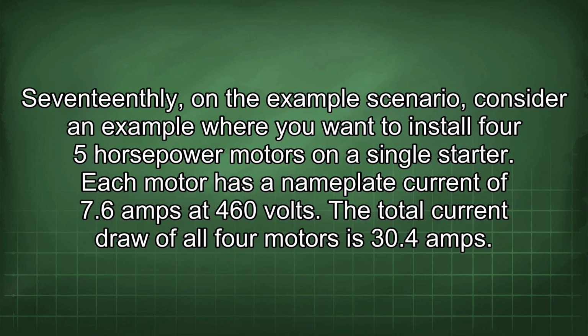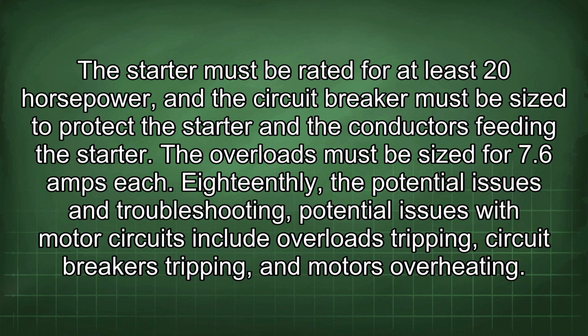17thly, on the example scenario, consider an example where you want to install 4 5 horsepower motors on a single starter. Each motor has a nameplate current of 7.6 amps at 460 volts. The total current draw of all 4 motors is 30.4 amps. The starter must be rated for at least 20 horsepower, and the circuit breaker must be sized to protect the starter and the conductors feeding the starter. The overloads must be sized for 7.6 amps each.